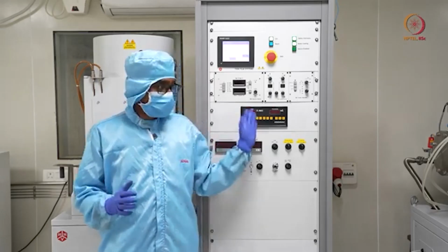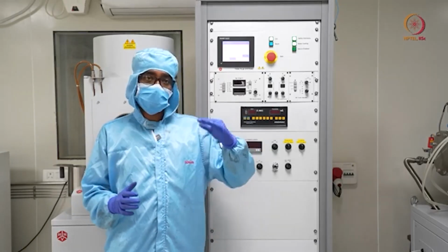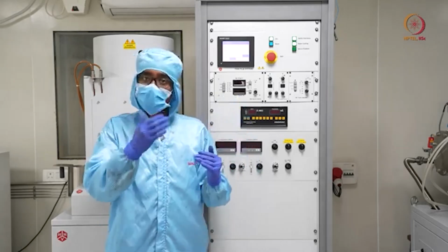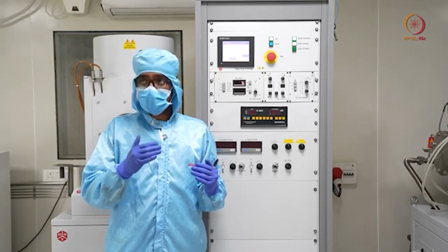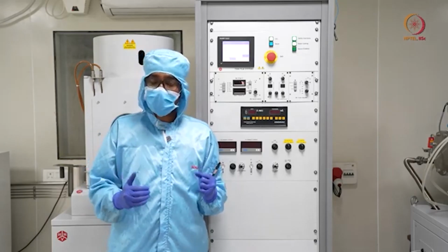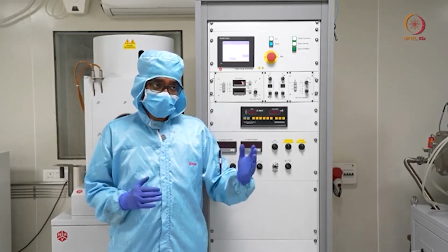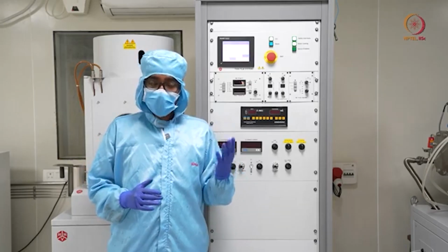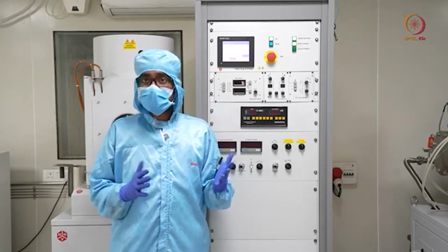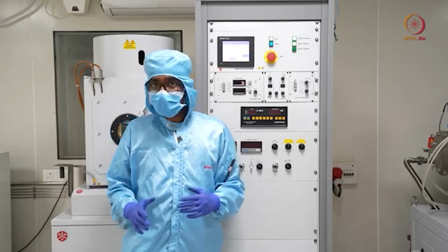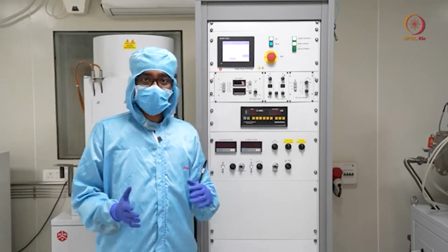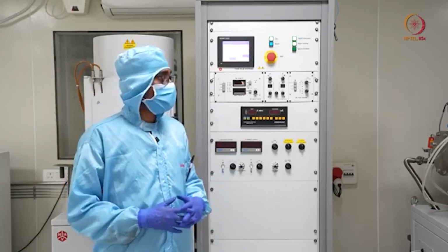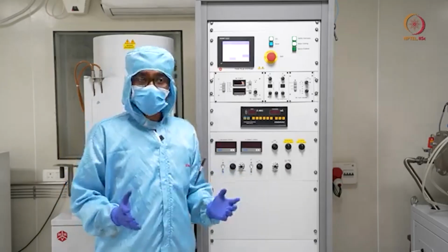For this tool we have this atmospheric pressure range, as well as when it is under vacuum we need to measure the e power -6 or e power -7 millibar range. So we have both. However, we cannot show you the Pirani gauges and penning gauges as of now, because then we would have to open this whole thing. We don't want to open the setup as of now. So these are the two types of gauges.